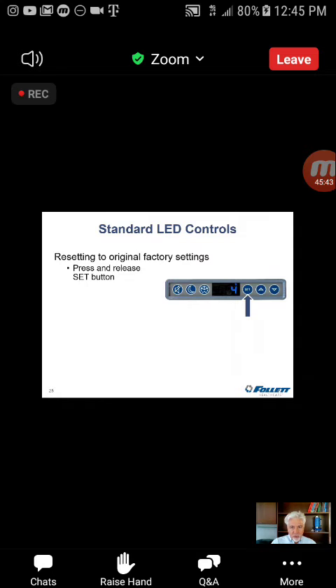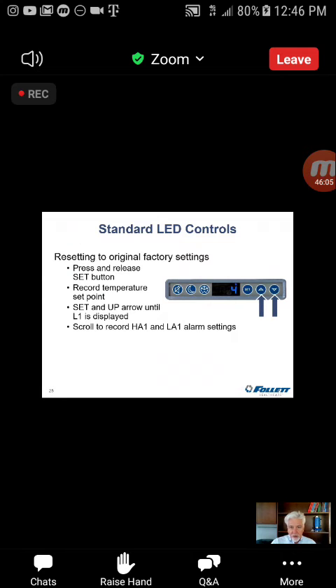First thing is there's some settings we need to know. We want to touch and release the set button so that we can see the set point. We should record that. It may not be what we set it for here at the factory, depending upon what's being stored in the refrigerator. Once we've got that value, then we're going to go to the set and the up arrow, and we're going to go into level 1 of the hidden menus. And we're going to check the alarm settings. The alarm settings are normally set during startup, which is why we're not covering them here today.